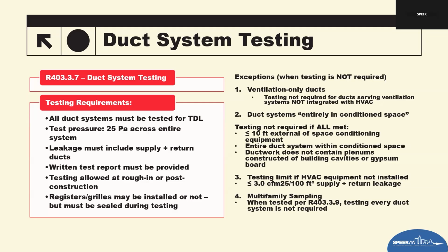Basically, it says you need to have no more than 10 feet outside of the conditioned space. This is clarifying what happens if we have just a duct that bends in and out over a patio and comes back. If it's less than 10 feet, we still consider all of it in conditioned space. Therefore, we have a different testing allowance, or leakage allowance, to actually meet.